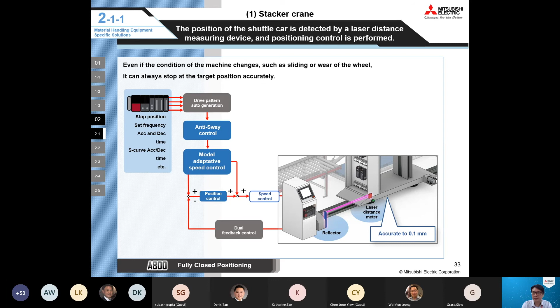In terms of safety, the operation can be stopped safely even in the event of an interruption of communication. For example, look at this feedback data mismatch: if a product falls in between the laser distance meter and the reflector, the distance data the meter is measuring will change suddenly. The inverter will realize there's a feedback data mismatch when they compare this with the encoder, so the operation can be stopped safely in the event of such an interruption.